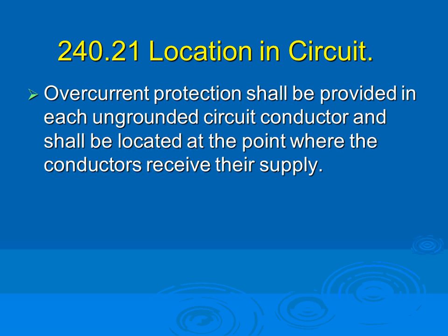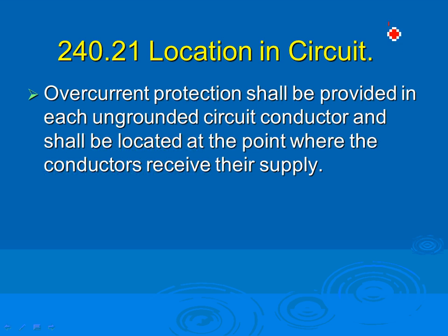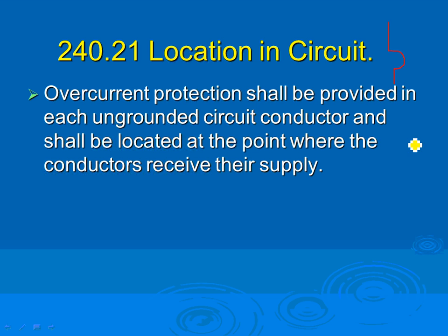Overcurrent protection device, guys: you must put the overcurrent protection device ahead of the conductor. So when you size, and this is not true in all conditions, here's my overcurrent protection device inside the panel. When I want to size my conductors, you're going to go, let me see if I can get the yellow, if it works here.